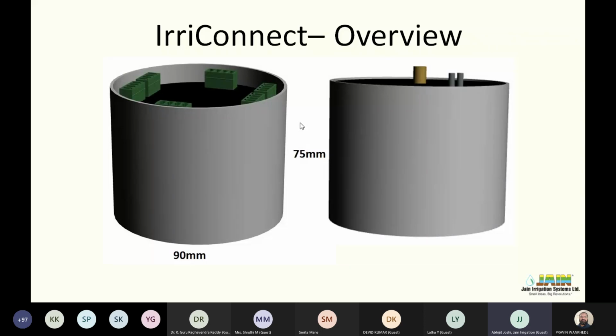So we developed a magnetic switch. We put it in the diaphragm of the valve, and as soon as the diaphragm moves a little, the magnetic switch changes its position from NO to NC, and we call this a valve confirmation sensing - it immediately confirms that the valve is in operation. The advantage is that you now confirm the valve is really in operation, not only electronically, but that water is actually going through the valve.